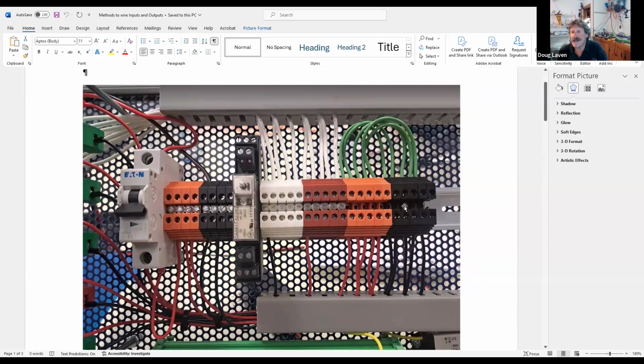There can be some limitations to that. For instance, if you wanted everything current sinking, a term we use, or everything current sourcing, it all depends on how you tie things up to the power supply. In this case, everything here is tied back to the common side of the power supply, so each of the loads is going to be sourcing the power. That means you have to tie the loads up to plus 24 volts, and this completes the path.